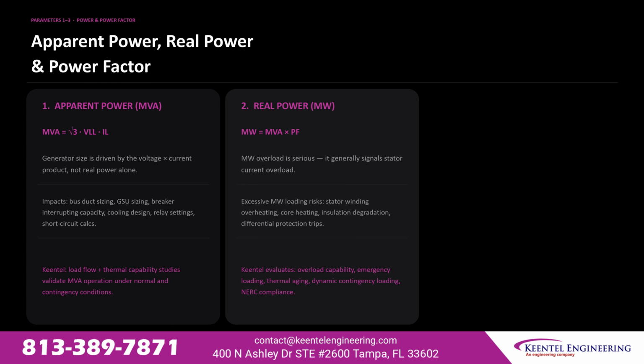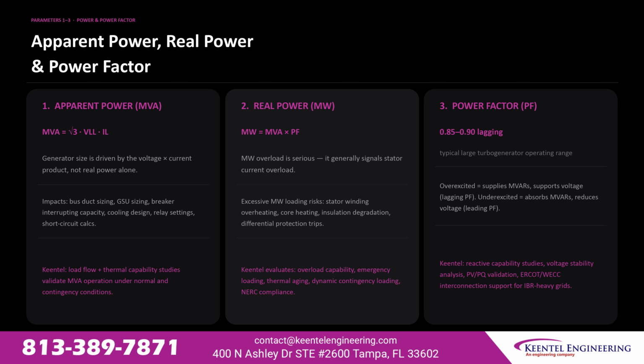Apparent power, measured in megavolt amperes, drives generator size based on the voltage and current product, not real power alone. It impacts bus duct sizing, generator step-up transformer sizing, breaker interrupting capacity, cooling design, and relay settings. Real power, measured in megawatts, equals megavolt amperes times power factor. Megawatt overload is serious. It generally signals stator current overload, risking winding overheating and insulation degradation. Power factor for large turbo generators typically runs 0.85 to 0.90 lagging.